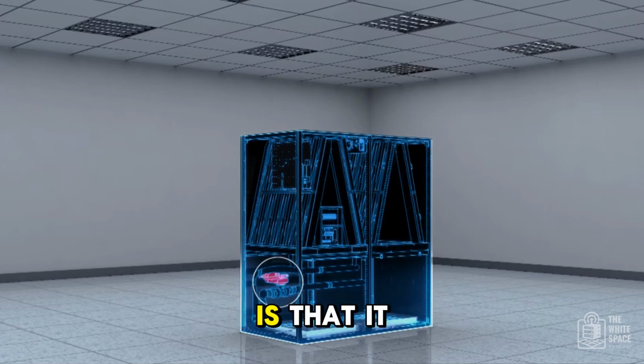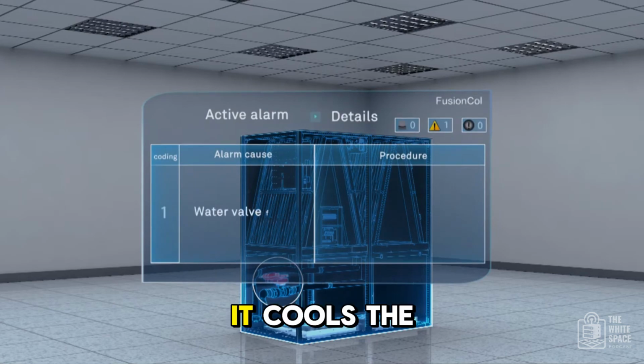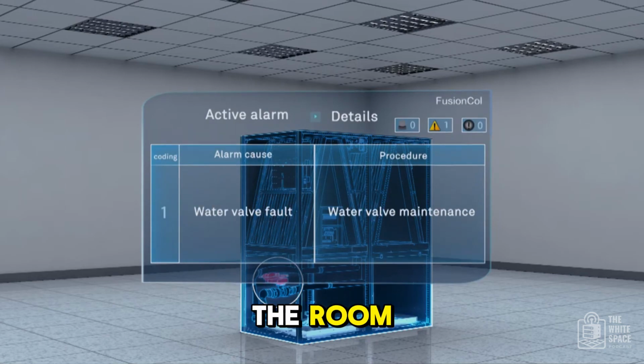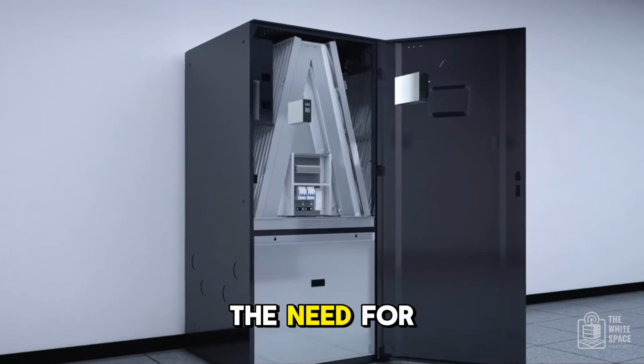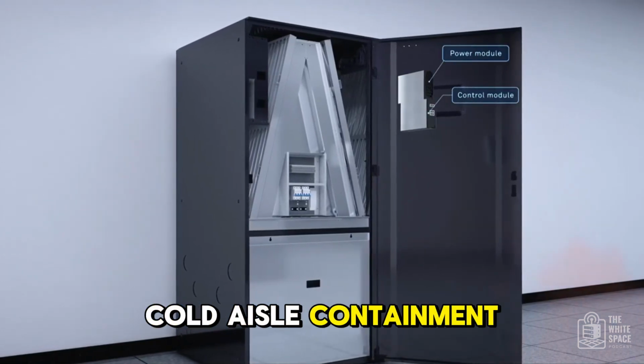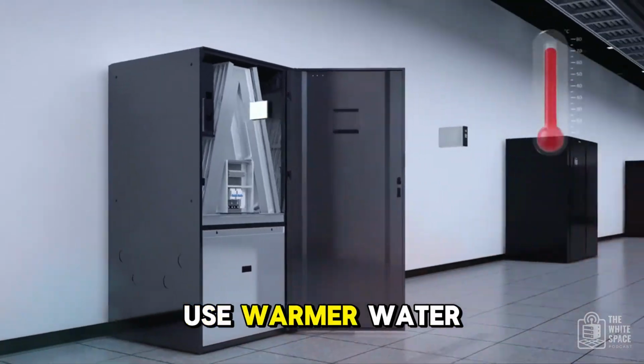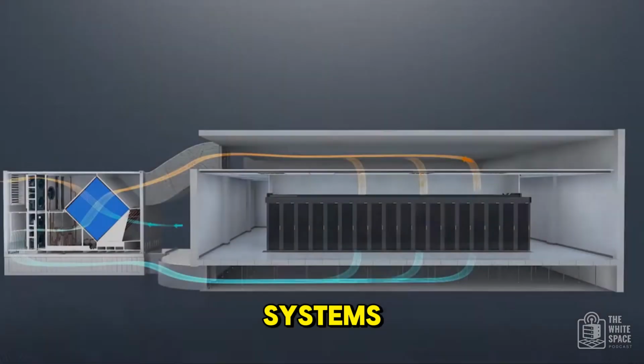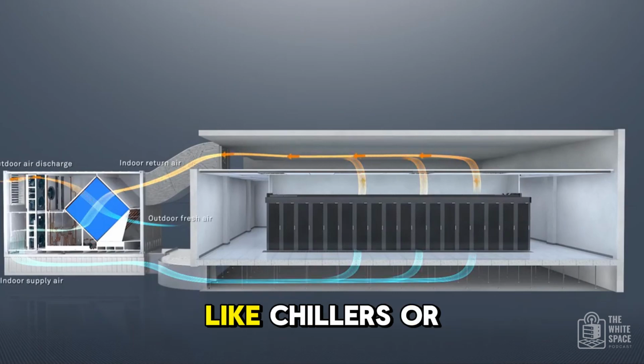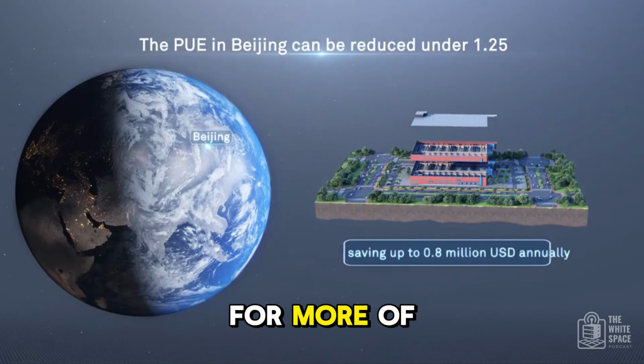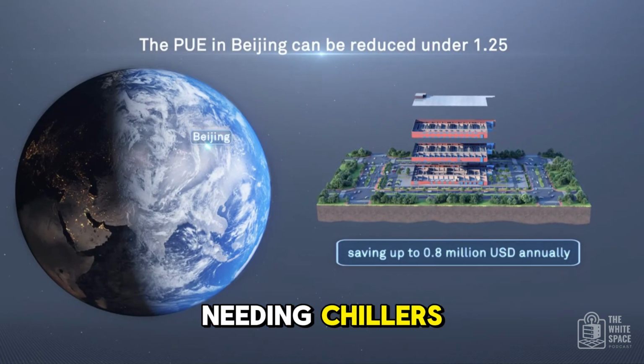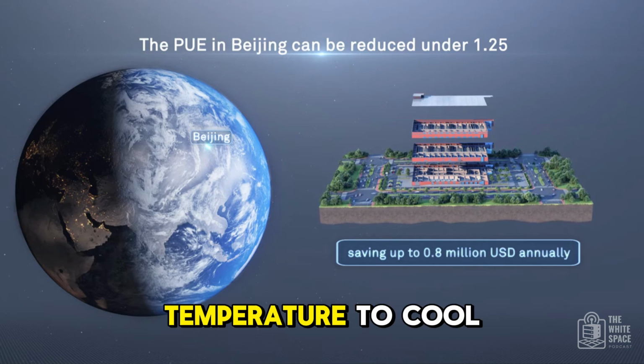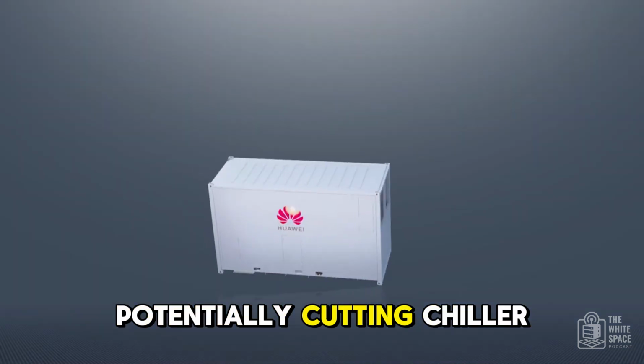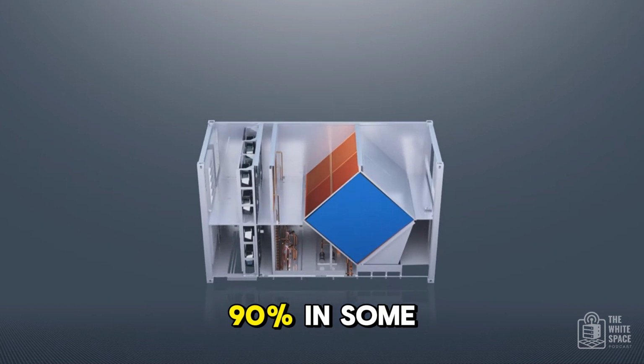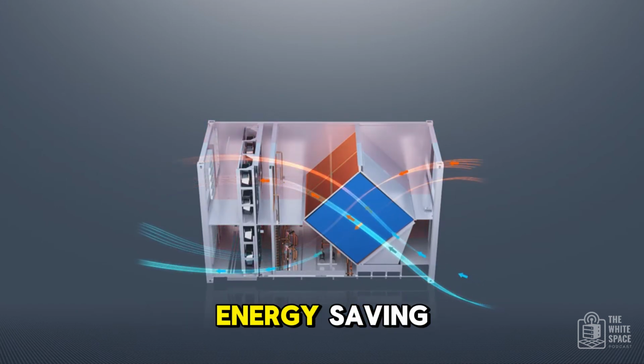A huge plus is that it negates heat at the source. It cools the air before it mixes back into the room. This reduces or even eliminates the need for complex hot aisle, cold aisle containment setups. It also means you can often use warmer water in the cooling loop compared to other systems. This makes your external heat rejection, like chillers or cooling towers, much more efficient. It can even enable free cooling for more of the year. Free cooling, you mean like not needing chillers? Exactly. Using ambient air temperature to cool the water loop, potentially cutting chiller energy use by over 90% in some climates and setups. That's a massive energy saving.